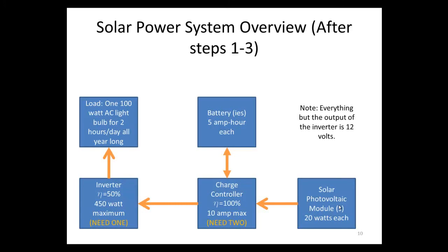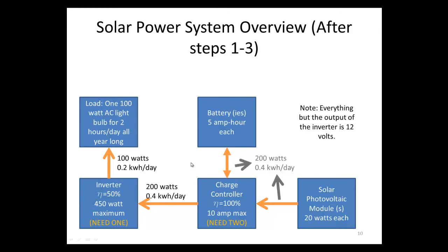To review what we've done so far: we found that we need one inverter and two charge controllers. Going to the load is 100 watts when it's on, and the energy needed is 0.2 kilowatt hours per day. When the light bulb is on, the inverter is drawing 200 watts from the charge controller, and the energy coming from the charge controller is 0.4 kilowatt hours per day. This means we need to supply — either from the battery or from the solar module — 0.4 kilowatt hours per day.